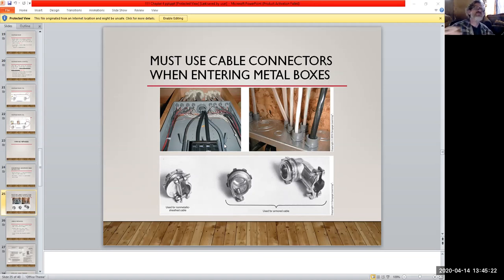Like I said earlier, your number 14 sheathed cable is, of course, going to be a different size than your number 12 sheathed cable. So you have to match up your connectors and couplings and stuff like that to make sure it's the right size. And they have it always printed, you get the box of these, 5/8, 3/8, and that kind of thing. Just make sure you got the right sizes for your stuff. If you don't, then it's not going to work, and you would never pass an actual inspection because you wouldn't be able to pass the strain relief test.